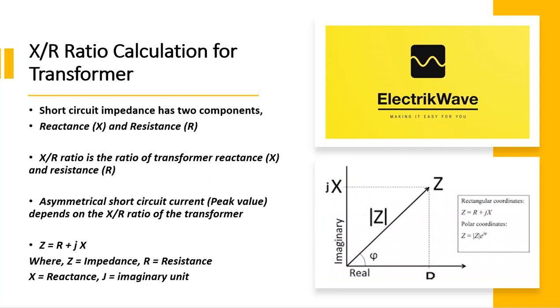Short circuit impedance has two components: reactance X and resistance R. X by R ratio is the ratio of transformer reactance X and resistance R. Asymmetrical short circuit current peak value depends on the X by R ratio of the transformer. Z equals R plus jX.